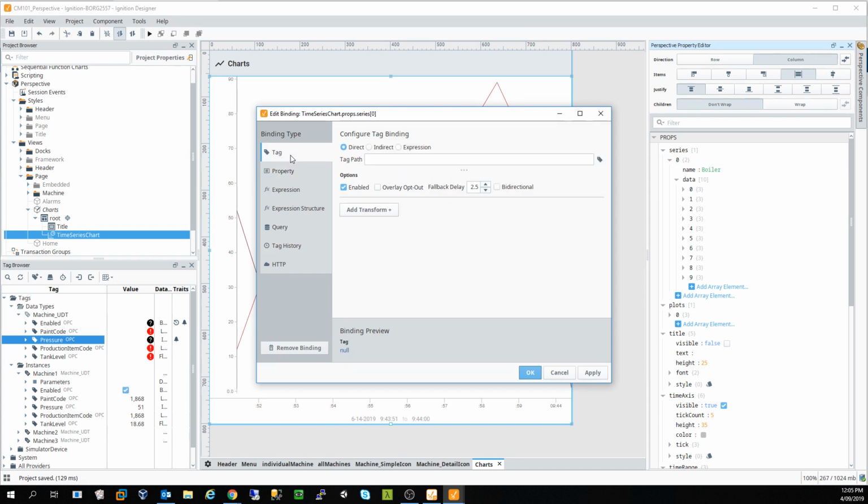Although we could, if it was a short time series tag, like a sparkline, we could actually monitor the tag all the time the client is open or the runtime is open. The values are cached, and that sparkline would be read and aggregated directly from the I/O and wouldn't need a history backing behind it. But generally speaking, you would use tag history via the historian.